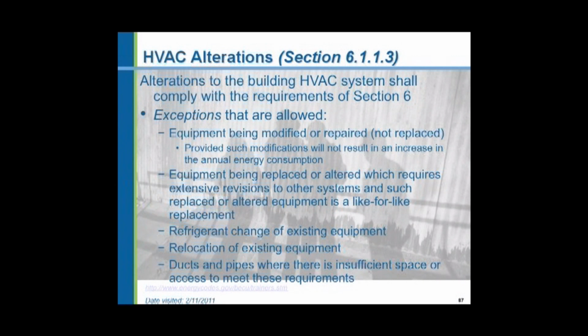Alterations have some exceptions. If you're repairing something, if you're putting a new fan motor in, if you're replacing the temperature controls or the burner controls or whatever, you do not need to bring the device up to the new energy standards if you're not going to reduce the efficiency. If you cannot get a new piece of equipment in without moving everything around in the mechanical room, revising ductwork, relocating controls, all sorts of other devices, if you cannot replace the equipment with new, highly efficient equipment, then you are allowed to replace it in like kind.